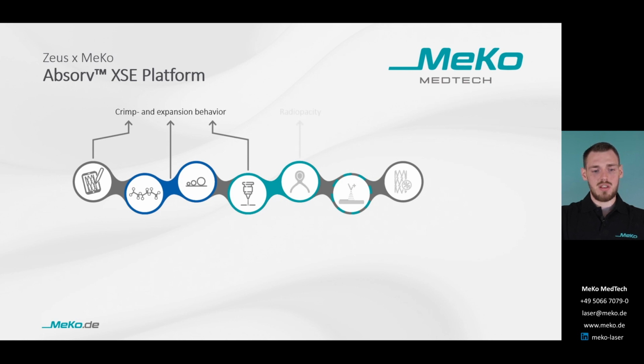Up to this point, the scaffold is not visible for the surgeon during the operation, and therefore markers can be inserted. The size depends on the density of the material used, and the location of the markers must be taken into account in the design planning already. For example, the marker eyelet should better be located in an area that is not severely deformed during crimping or expansion of the device. Frequently used marker materials are gold, platinum or tantalum, as those materials have a very high density and also a good biocompatibility.